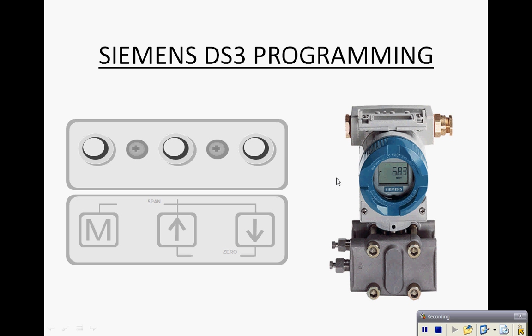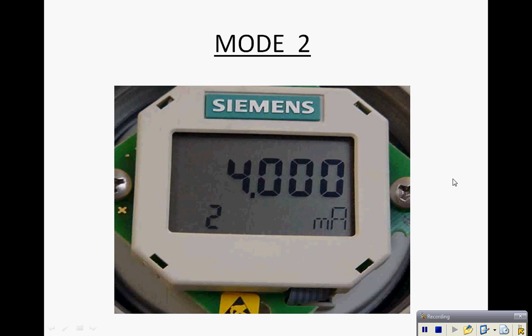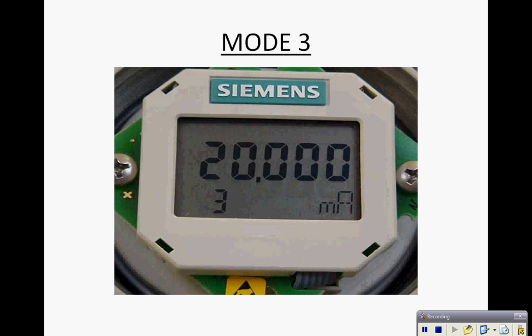Mode 1 on the transmitter is just the actual display. Mode 2 is where we set the zero with a pressure source applied at 4 milliamps. Mode 3 is where we set full scale with a pressure source applied.